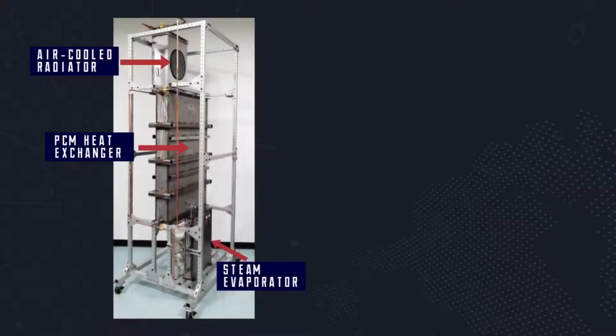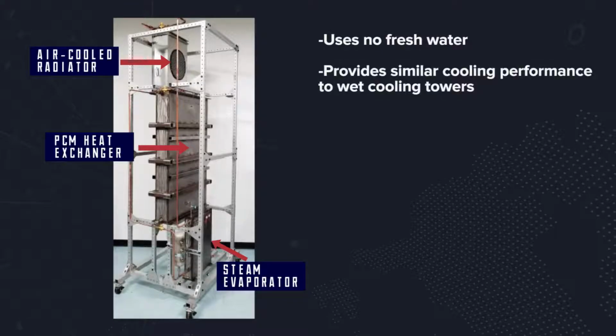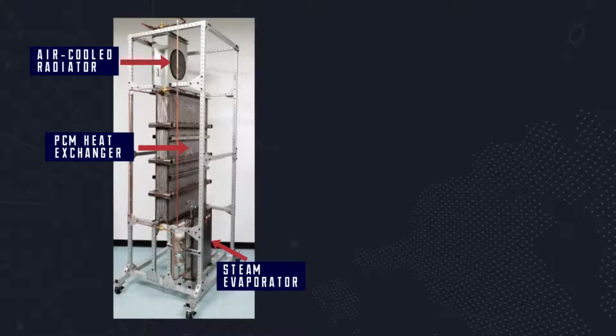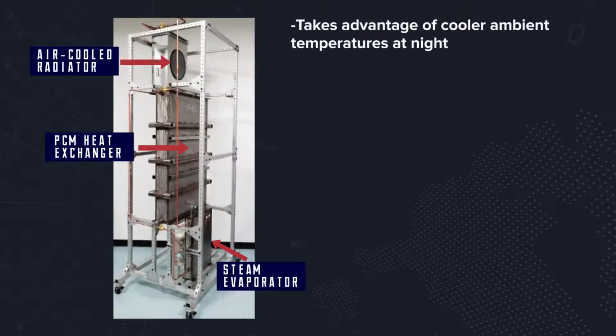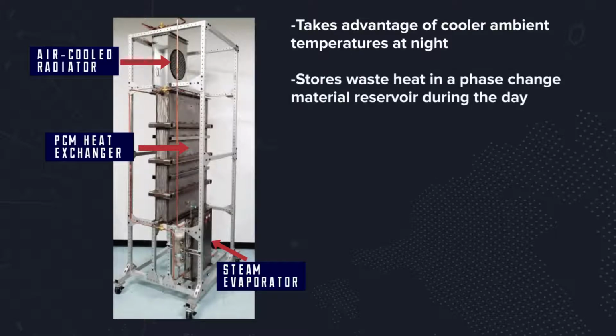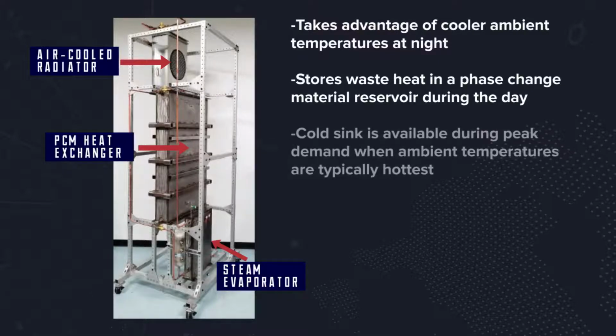ACT's supplemental thermal storage system for power plant dry cooling uses no fresh water while providing similar cooling performance to wet cooling towers. The supplemental system takes advantage of cooler ambient temperatures found at night and stores waste heat in a phase change material reservoir during the day. By doing this, the power plant is able to have a cold sink available during peak demand when the ambient temperature is typically the hottest.